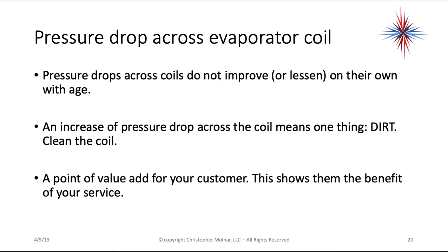Pressure drop across an evaporator coil is very important as well. Coils do not improve or lessen on their own with age — the older it gets, it doesn't get better. An increase in pressure drop across a coil means one thing: dirt. Clean the coil. This is another value-add point for your customer. If you come in on a preventative visit or service call, take a pressure reading across the coil, and if it shows higher than normal pressure drop, clean that coil and show the customer that you increased airflow by a measurable percentage.